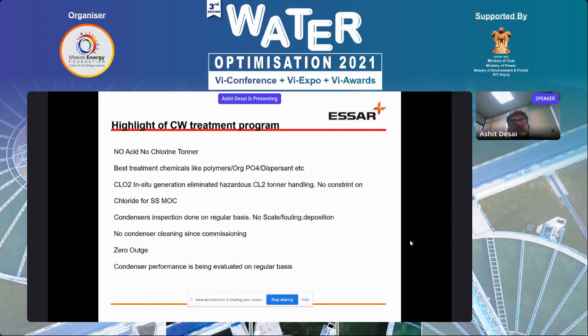Now, this is a unique cooling water treatment that we have designed here. I'm not sure, but as per my knowledge, none of the power stations in India will have this kind of thing. No acid: zero drop of acid is being used in the cooling water treatment program. Normally, every power station uses sulfuric acid to maintain pH and to maintain ASI, LSI, Ryznar index, etc. We don't use a single drop of acid in the cooling tower. We have eliminated chlorine tonners, which are very hazardous in nature, by implementing chlorine dioxide in situ generation. We are using the best of the available cooling water treatment chemicals, like high-grade polymers, that is terpolymers, and organic phosphate, that is PBTC. Normally, the cost of these phosphates is almost 4 or 5 times more than the conventional phosphate treatment program.